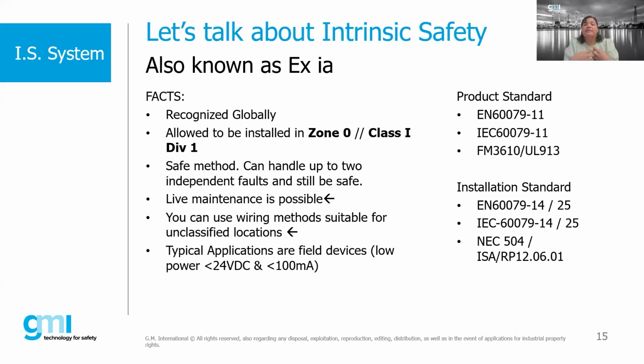Another thing that we have to recognize is that intrinsic safety is the protection method that is allowed on Zone 0, which is the highest risk environment in our hazardous locations, as well as Class 1 Div 1. So it can go all the way into that area where you always have that exposure of explosive atmosphere. We say intrinsic safety is one of the safest protection methods. And I want to clarify, every single protection method is safe when you utilize it properly. But intrinsic safety can withstand 2 independent faults and still be safe. So I think that's one of the reasons why it's allowed in these higher risk environments.